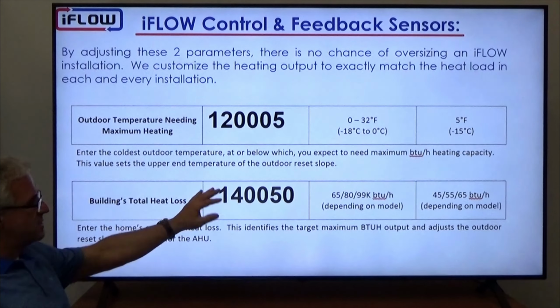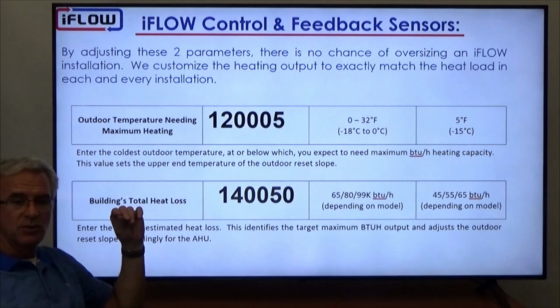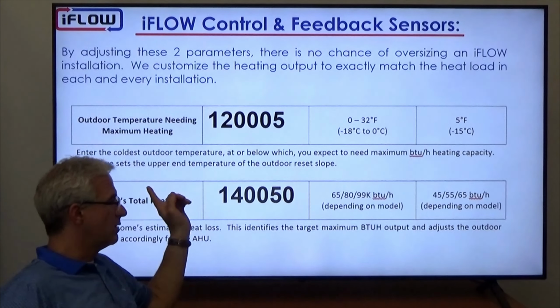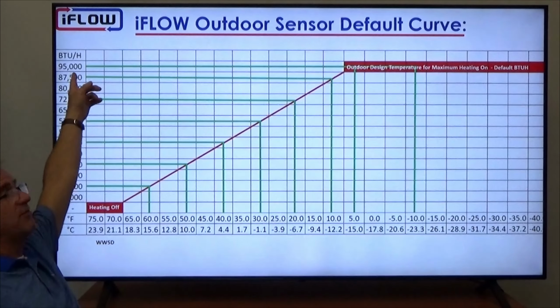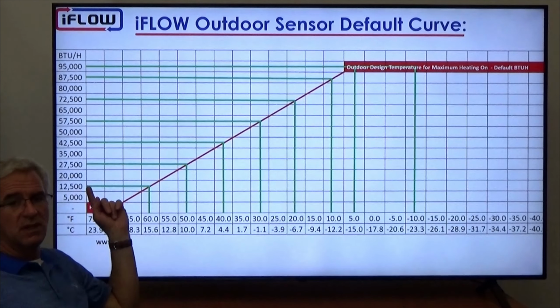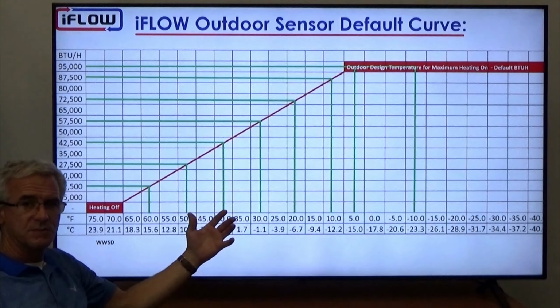Then in parameter 14, we enter the heat load of the building. So even though the iFLOW that we were looking at can do 95,000 BTUs, maybe we're installing it into a home that only has 15,000 BTUs.